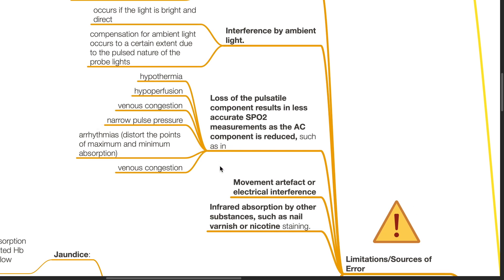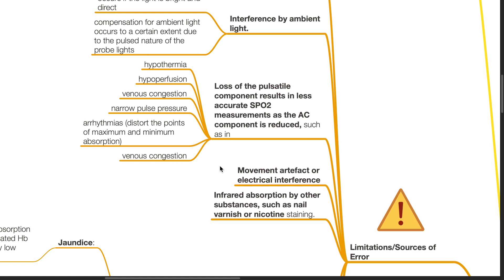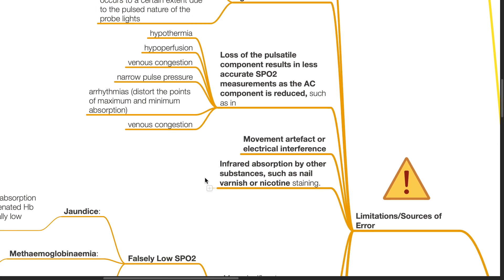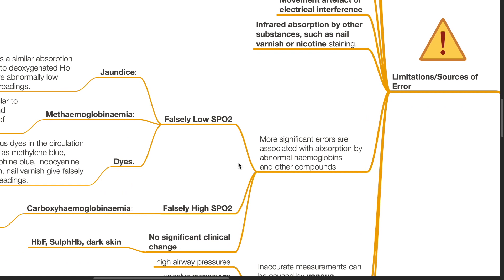Movement artifact or electrical interference can interfere with the accuracy of SpO2 measurements. Infrared absorption by other substances such as nail varnish or nicotine staining can affect the accuracy of SpO2. More significant errors are associated with absorption by abnormal hemoglobins and other compounds.